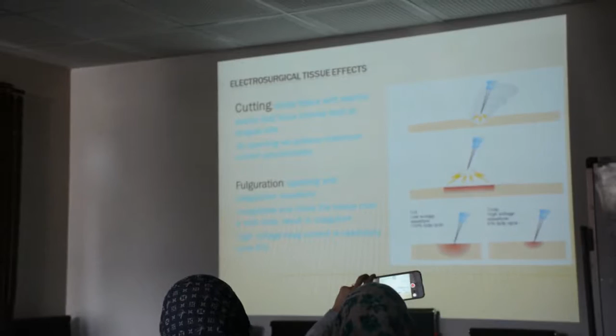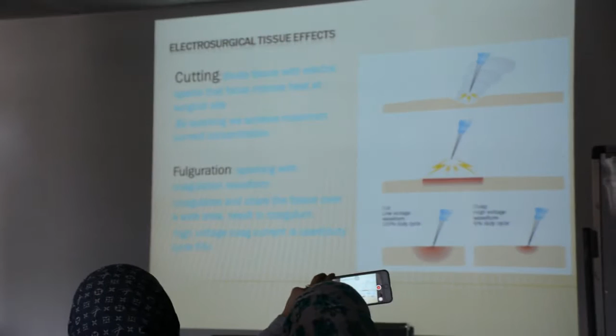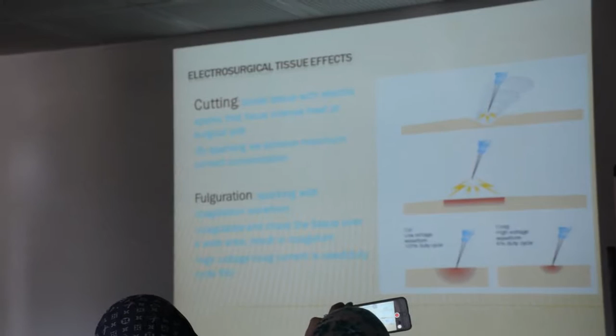Electrosurgical tissue effects: cutting divides tissue with electric sparks that focus intense heat at the surgical site. By sparking, we achieve maximum current concentration. Fulguration: sparking with coagulation waveform coagulates and chars the tissue over a wide area. To result in coagulum, high voltage coagulation current is used. Duty cycle 6%.